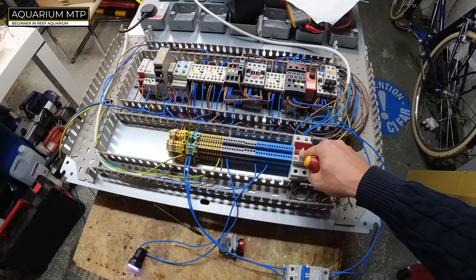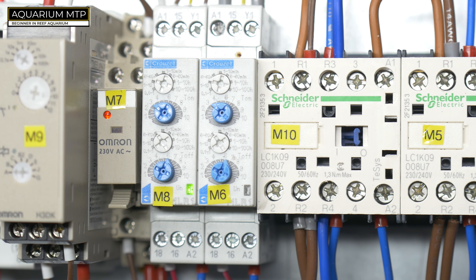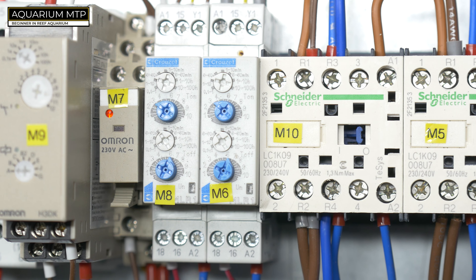The aquarium is gone. The UPS is now beeping, indicating there's no mains power supply. You should be able to see the M8 timer flashing — and you may be able to hear when it actually makes contact. Now we're going to turn on the generator.